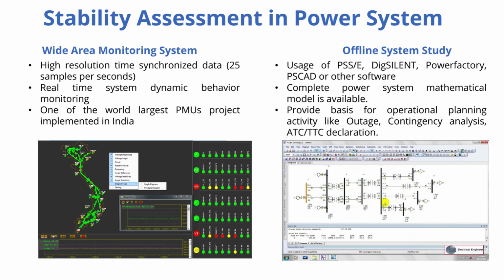Long-term planning, designing system upgrades, planning outages, performing exhaustive contingency analysis, simulating thousands of possible failures, and crucially, determining the safe power transfer limits, ATC-TTC, for key parts of the grid, ensuring all types of stability are maintained under various scenarios. They establish the operational rulebook. So offline studies define the safe operating boundaries, and SCADA is to help operators stay within them in real time. That's a good way to think about it.